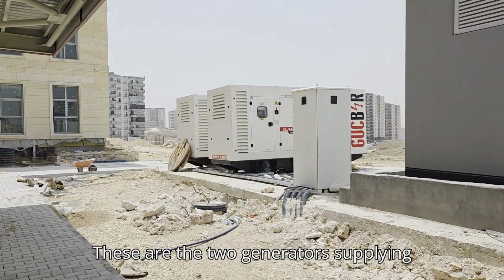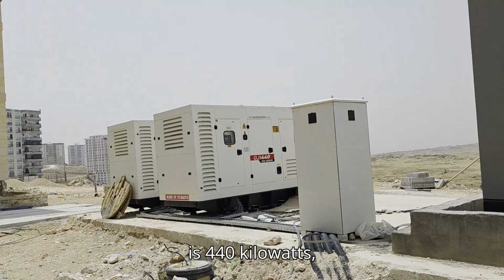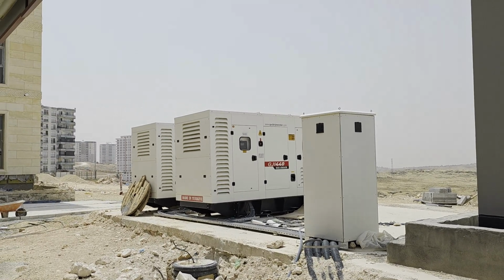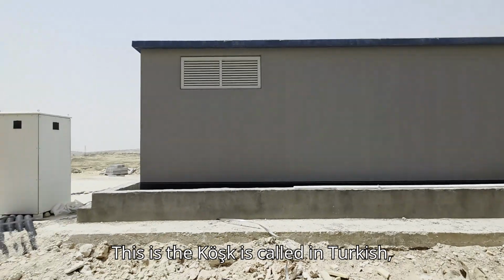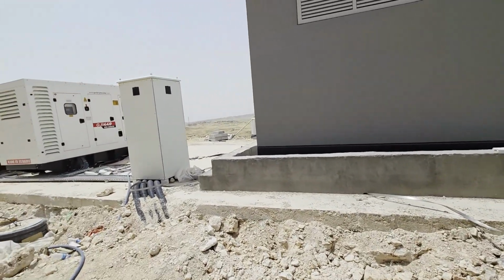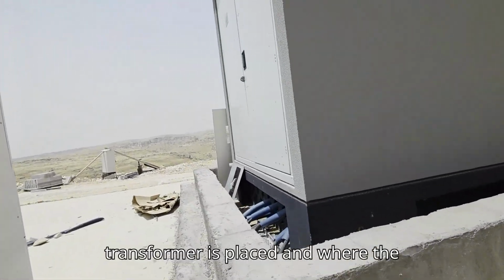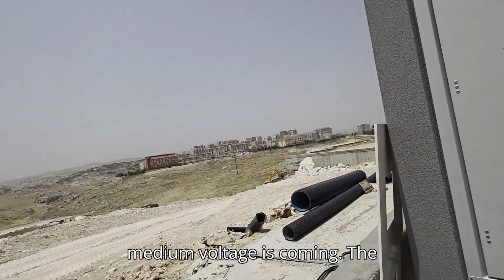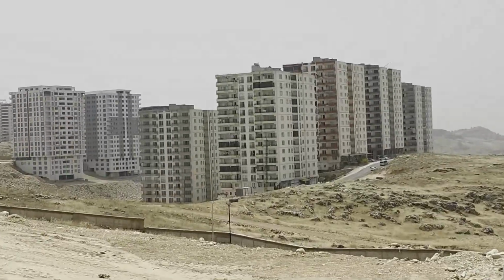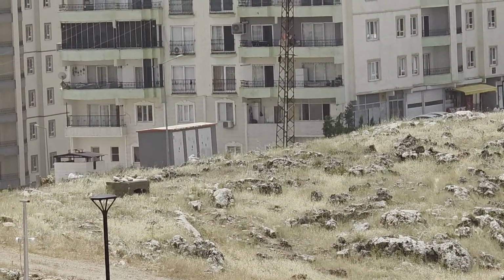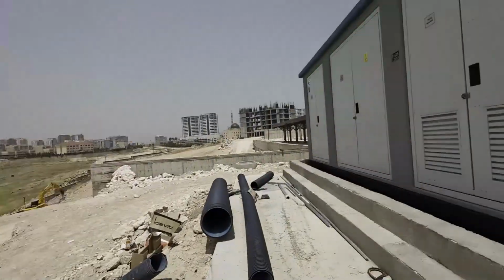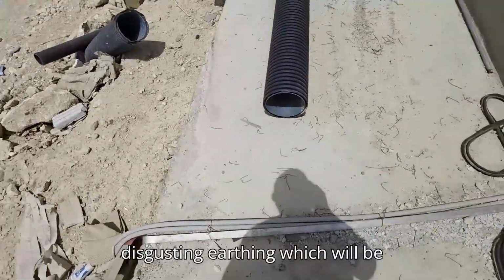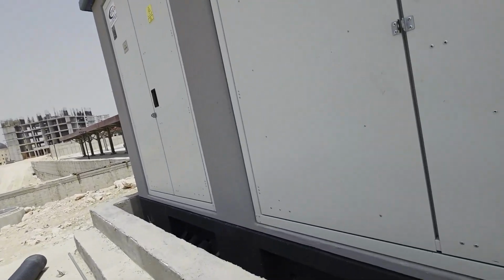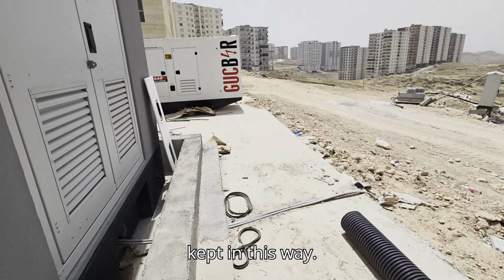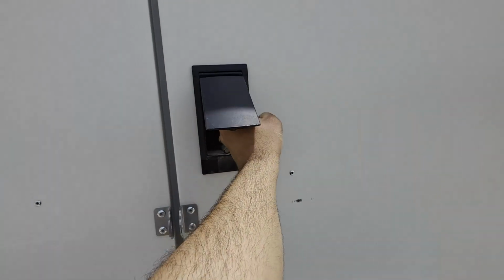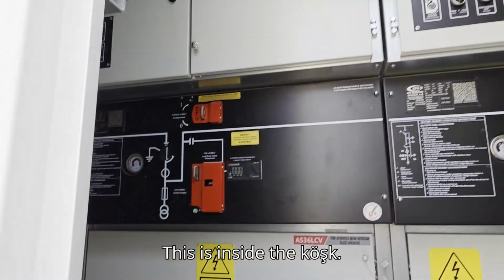These are the two generators supplying the whole building. Each one of them is 440 kilovolt ampere. This is the köşk, as it is called in Turkish, which is basically the place where the transformer is placed and where the medium voltage is coming. The medium voltage is coming from that köşk using XLPE cables. This is the disgusting earthing, which will be modified, of course, to not be kept in this way. This is inside the köşk.